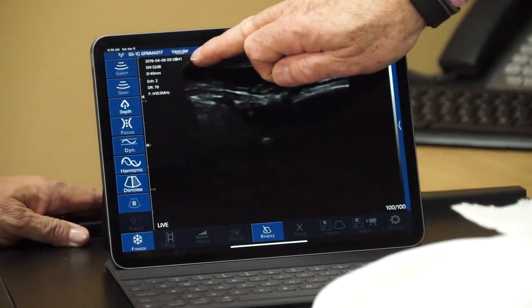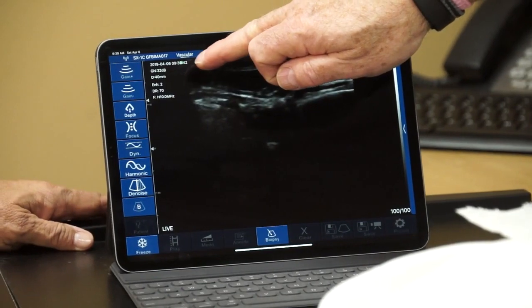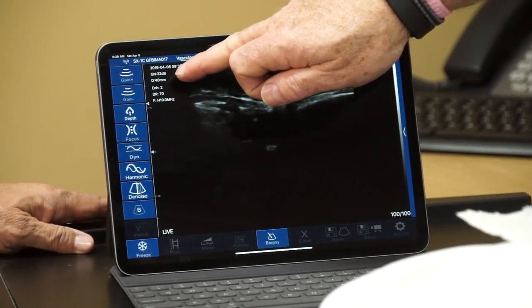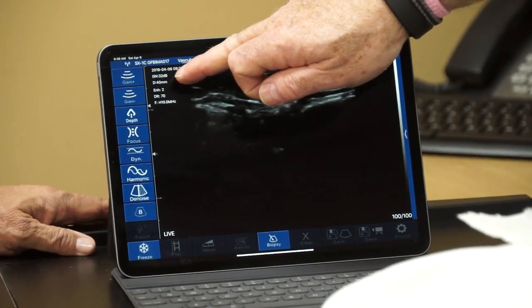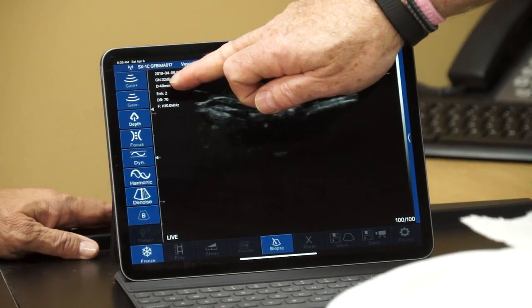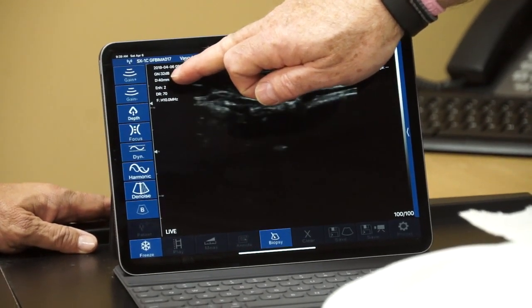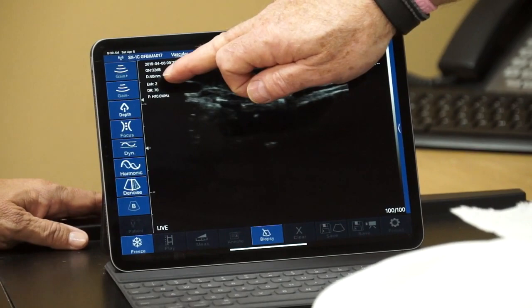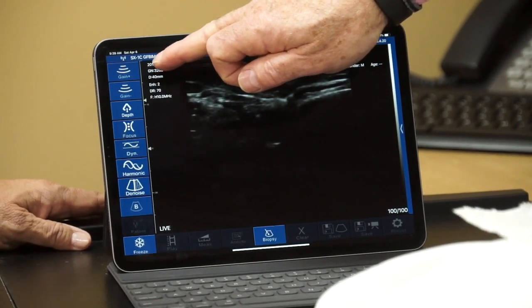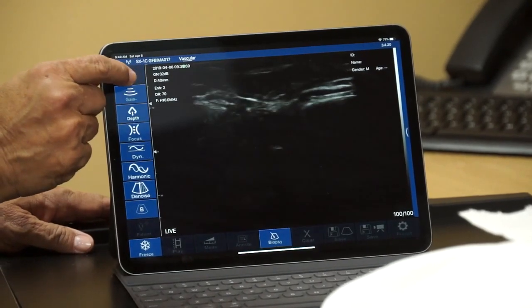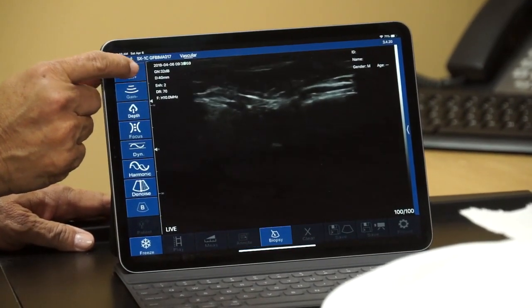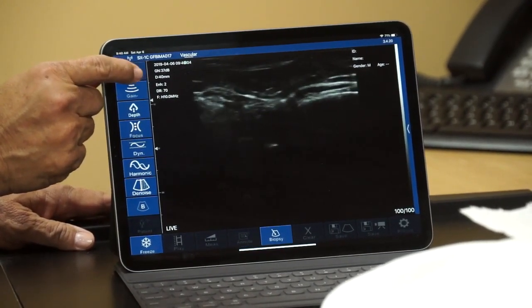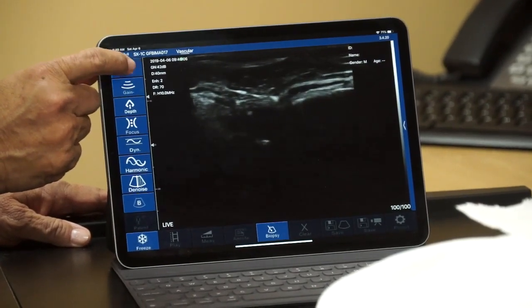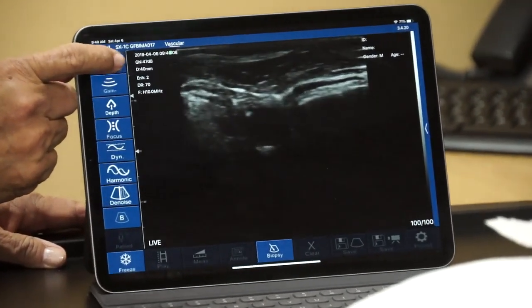The parameters are displayed in the upper left-hand corner of the viewing screen, and here we're monitoring the changes that occur to the number next to the letters GN for gain. Right now we're at a very low number of decibels for the gain. It's at 32. Dr. Garcia will be increasing the gain all the way up to its maximum, which I believe on this machine is 105. So now we're increasing. We should see the image brighten up as we go from the 30s all the way up towards 100.